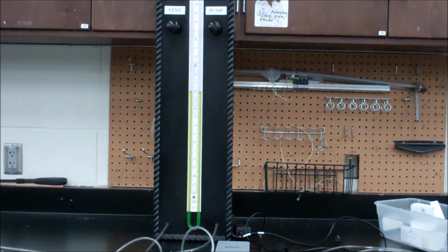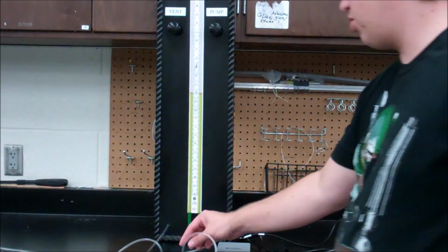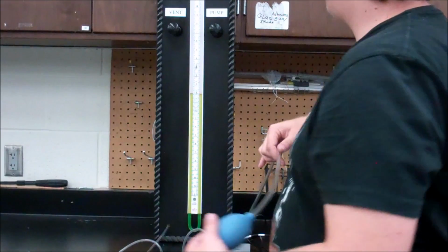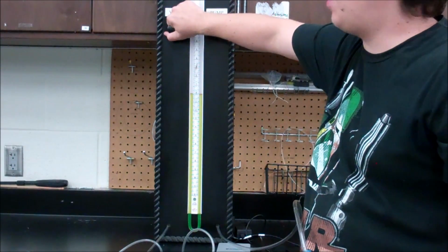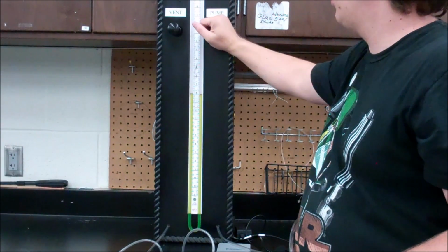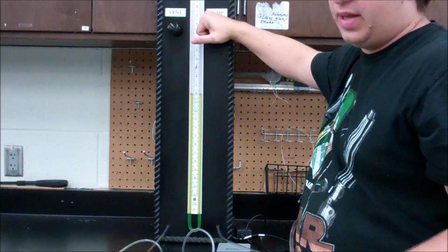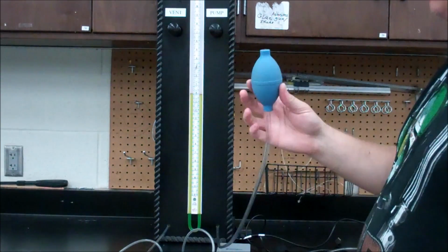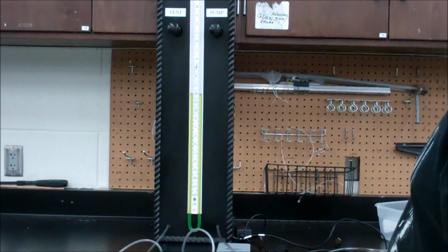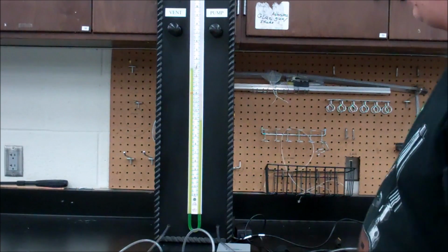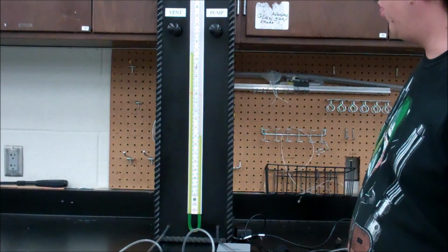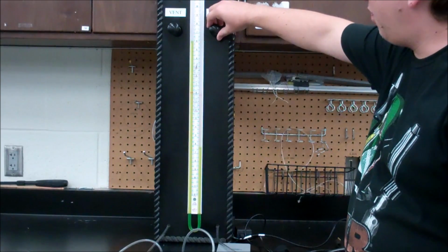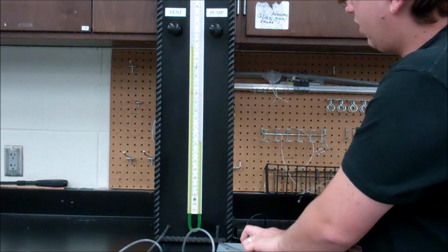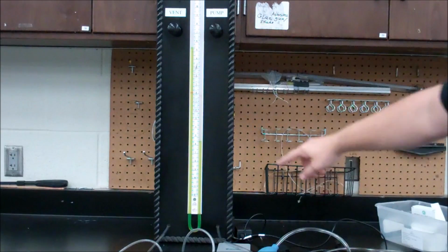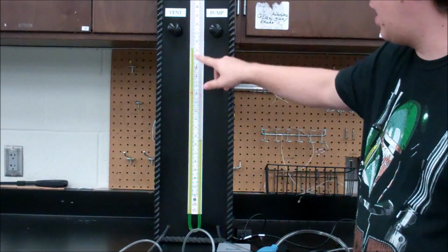Now that you have it at zero, what you want to do is make sure the pressure transducers are hooked up. Then what you're going to do is turn the vent valve to close all the way, open the pump valve a little bit to the left, and then you're going to use the little pump connected to it to apply a pressure. And you can see that the fluid moves. Now you're going to pump to just over 10 inches of water column, which is +5 to -5.